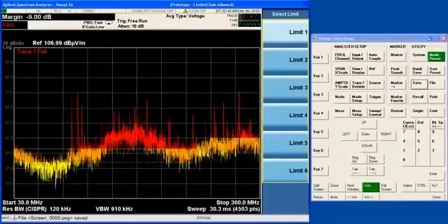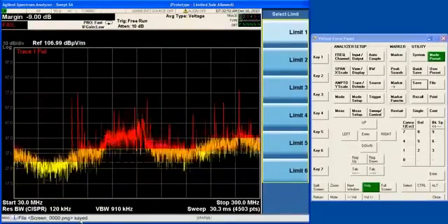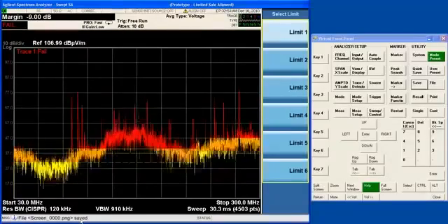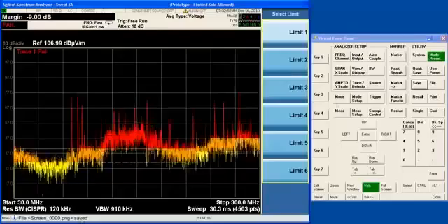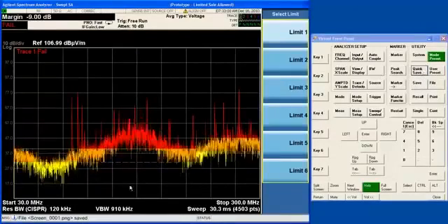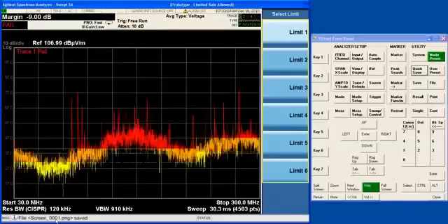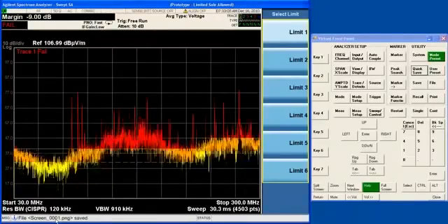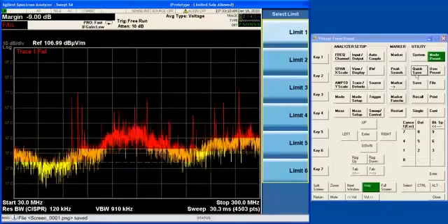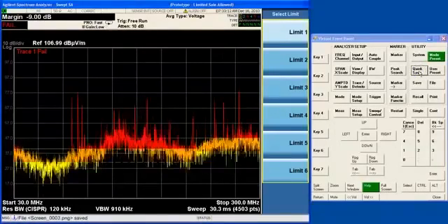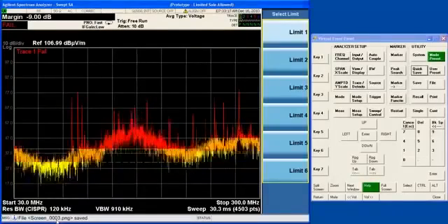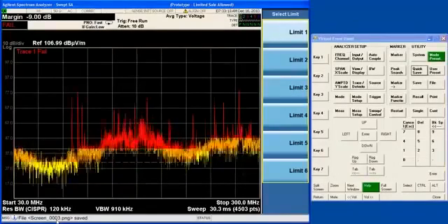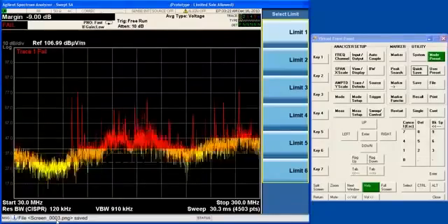And once you have saved a file type, whether it be a screen image or a state or a trace, the next time you push the Quick Save button, it saves another file just like the one you previously saved. So if you want to save screens, it is easy to do screen dumps all day by just continuing to hit the Quick Save button. And it simply increments the suffix in the file name, making it really easy for you to do screen dumps at any time.